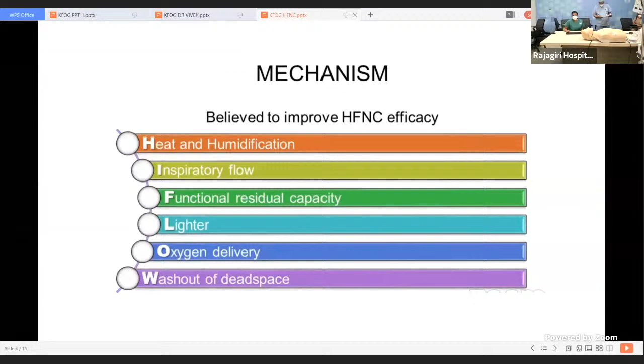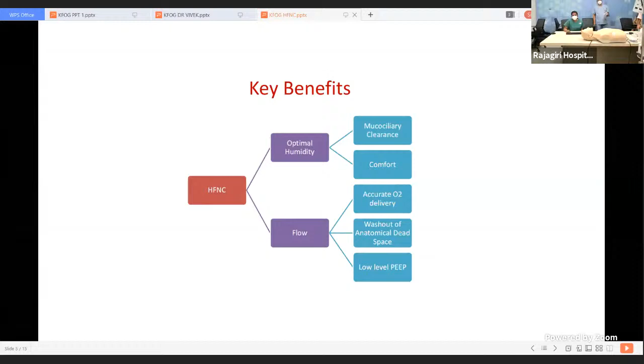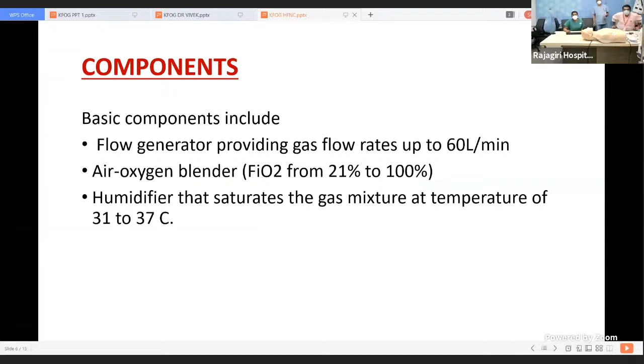And as I already mentioned, the oxygen delivery is fixed with HFNO and it helps in washout of dead space. So the key benefit is that with optimal humidity, we are getting mucociliary clearance and patient comfort. And with adequate flow, we are getting accurate oxygen delivery, washout of anatomical dead space and a low level of PEEP. So the basic components include a flow generator, an air oxygen blender and a humidifier. Okay, now my colleague will demonstrate the machine.